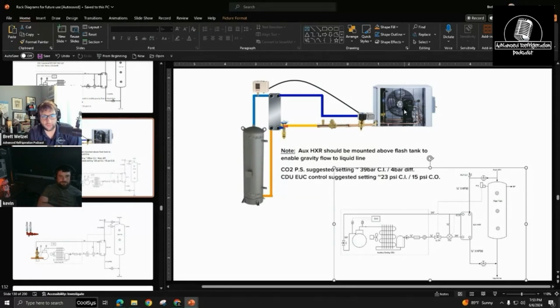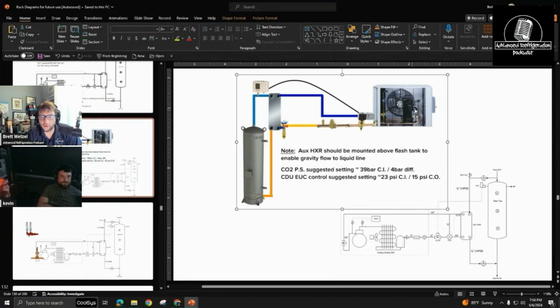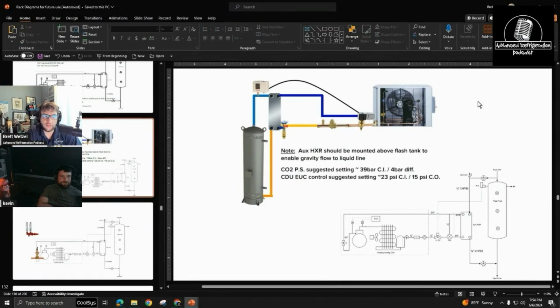The only caveat is, as Kevin would say, this guy would have to be on a generator. They use a mechanical pressure switch hooked up to the CO2 side, and it depends on the piping. On this one, they're suggesting you cut in at 39 bar with a 4-bar differential to cut in and out.